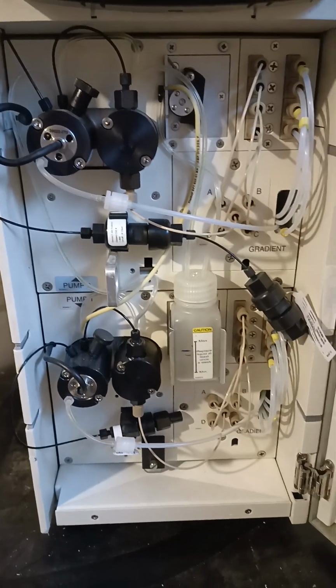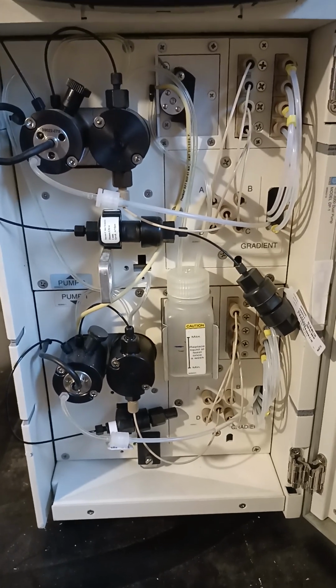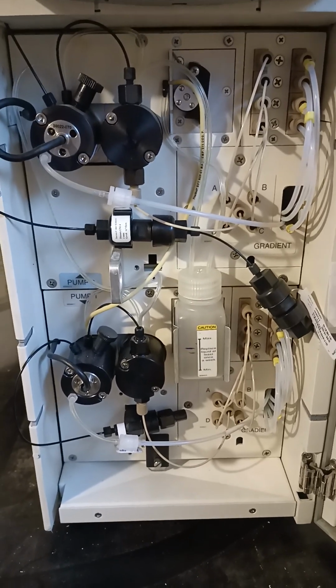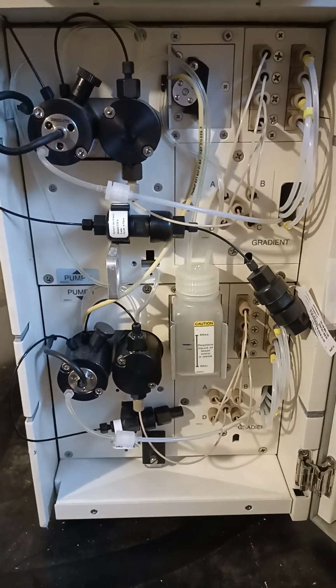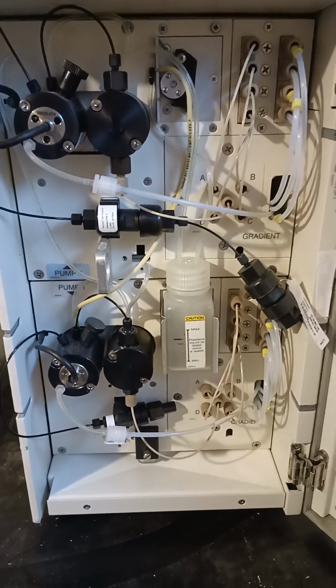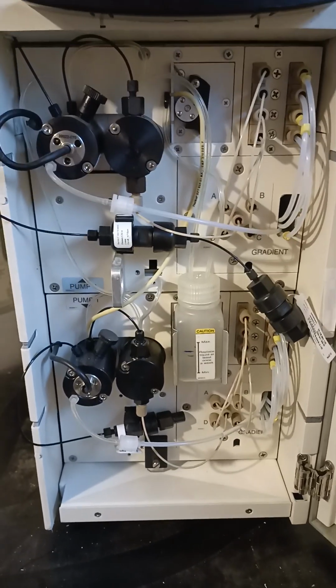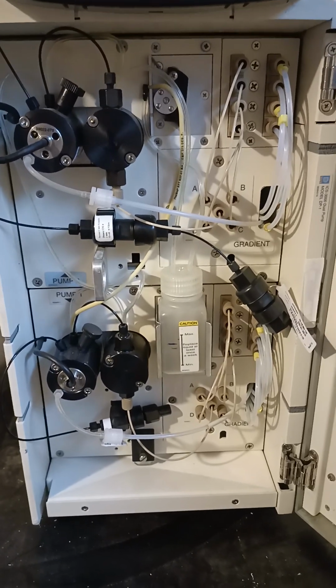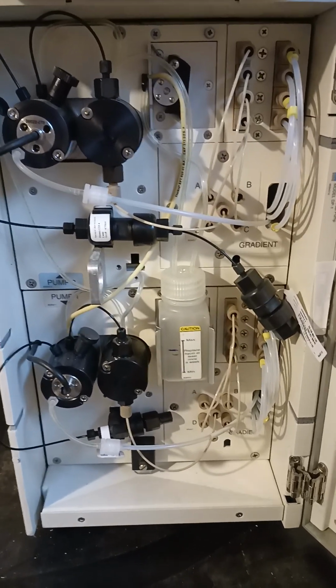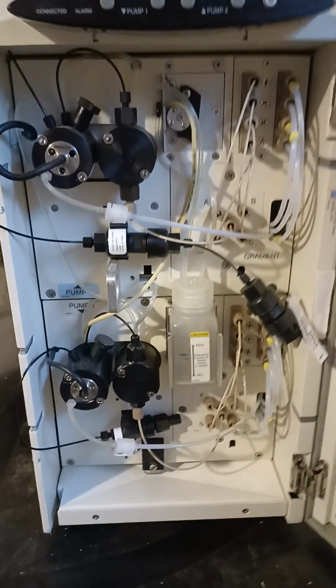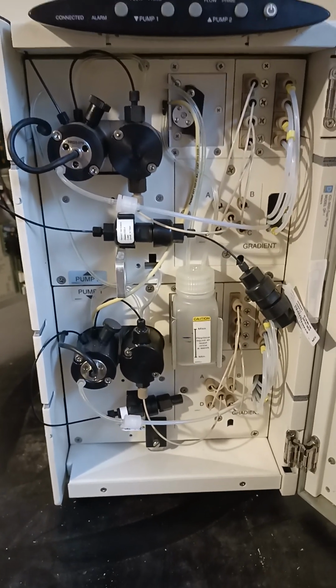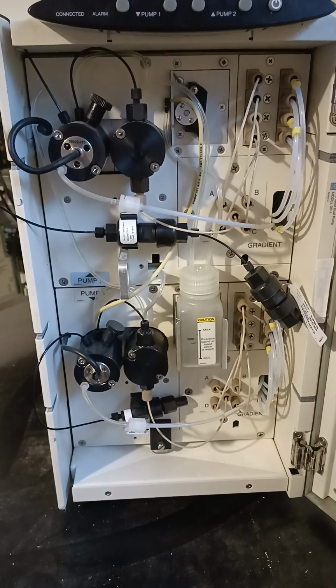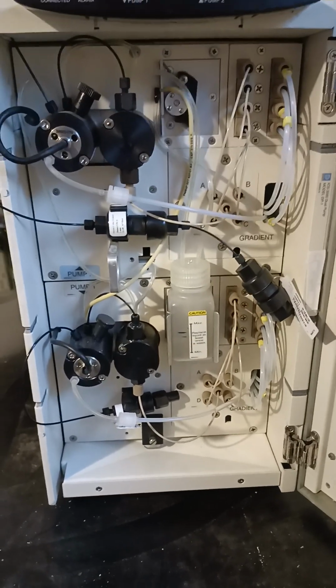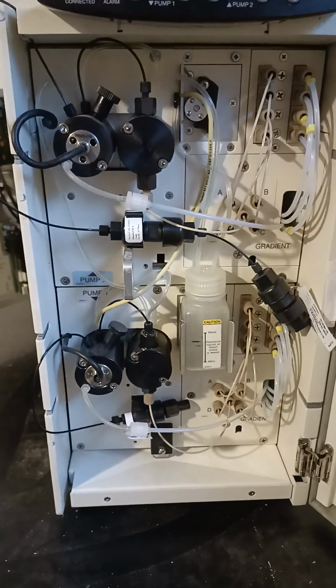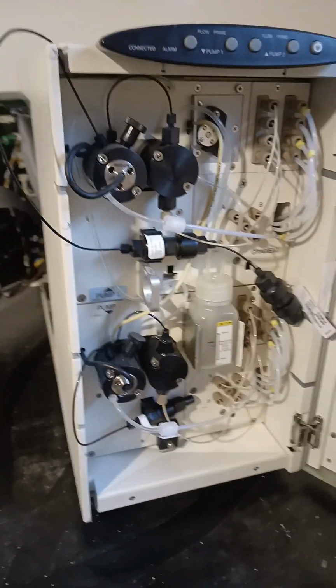But they're very similar. There's a few minor differences in the piston seals, and in my experience, the weak spots in these systems are the actual connectors or ferrules, which are tough to get sealed beyond 4,000. They have modern ferrules that are intended to be higher pressure, but in my experience, they don't work quite as well as they're supposed to, and you have to torque them down quite a bit, and it collapses some of the tubing.